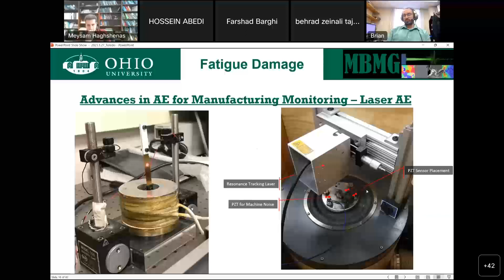So in the one on the left, this hangs from a fishing line, and a solenoid vibrates the material. In the case of the one on the right, it's using geometry to create a gauge section that is free from the effects of the clamping section itself. We've since developed a methodology to do this kind of loading with axial loads as well. And that allows us to test different modalities on the same shaker, which is quite beneficial.